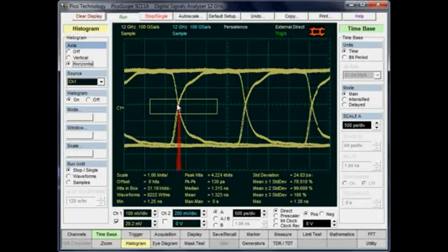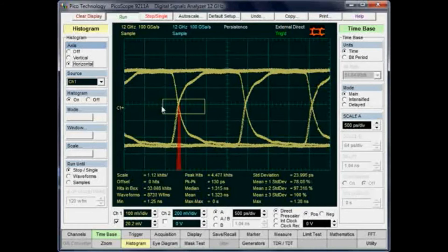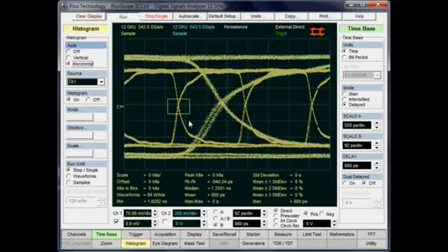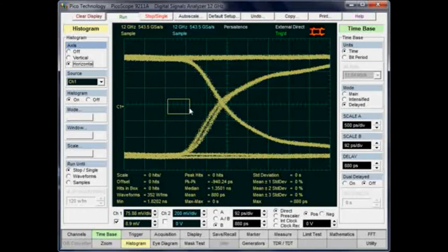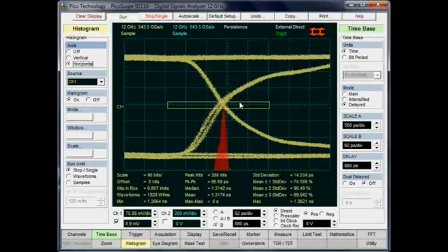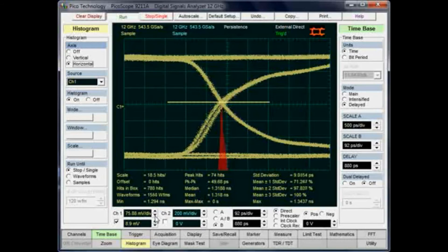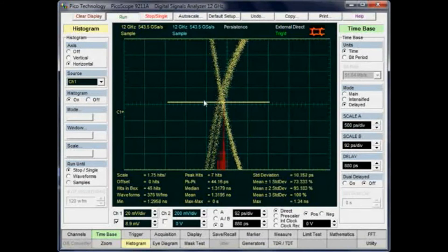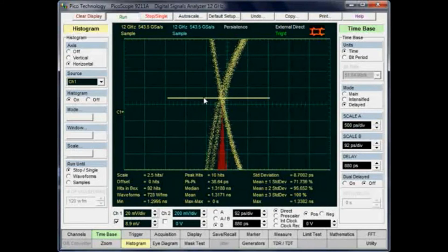We have a box where we can select where the measurement is being made. To get the most accurate measurement, it's often advisable to zoom in to that particular area and get the best acquisition. I'll move the measurement box very close in, zoom in on that particular crossing, and make my measurement exactly at the eye crossing point. It's also possible to increase the vertical resolution to get the best accuracy, adjusting slightly to find the optimum setting for this measurement.